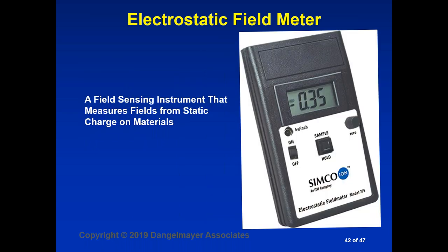What's the difference? Well, the difference is generally that an electrostatic field meter has a distance to viewing area ratio of about 4 to 1. But since the field meter makes measurements and is calibrated at 1 inch, when you look with an electric field meter at a surface, you're really looking at a 4 inch diameter circle on that surface. So basically, what you're looking at is a fairly large area.